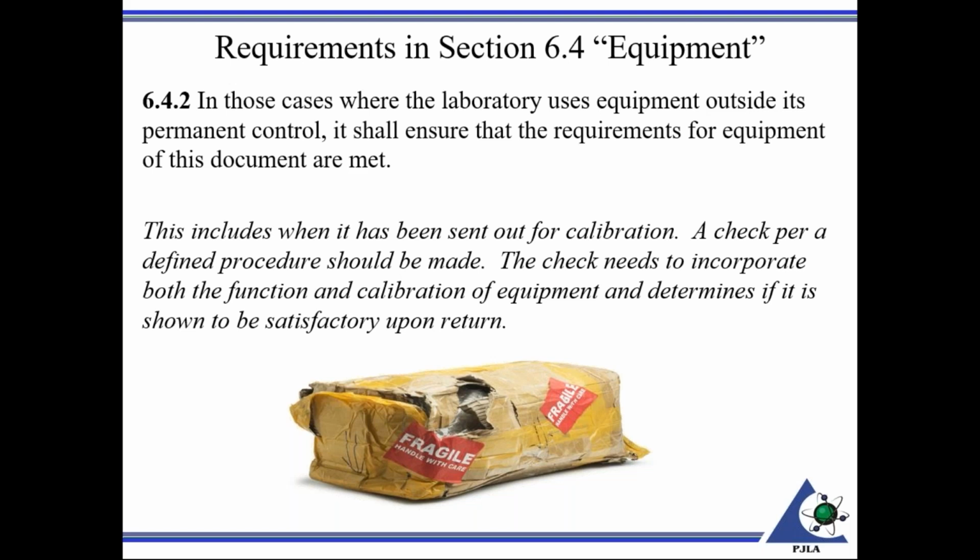So regarding this, a check per a defined procedure should be made before the equipment goes out that would incorporate both the function and calibration of the equipment, and determine if it's shown to be satisfactory upon return, i.e. some sort of checkpoint, some sort of check on the equipment where you can tell, when it is returned, if something has happened, if it is deviating from what the expected results would be.